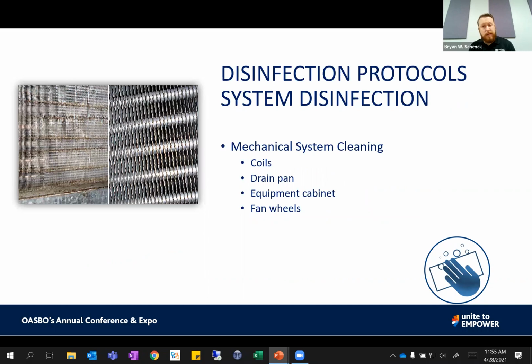Mechanical system cleaning. This is the disinfection piece. You want to make sure there are protocols in place to clean our systems. A lot of our preventative maintenance plans include cleaning our coils on the outside, but not cleaning the coils on the inside, which is where some of the bacteria, mold, and mildew could grow. I'm going to show that on the coil here on the left-hand side. That's when you start to have other pathogens that are not good for our air quality that might grow.